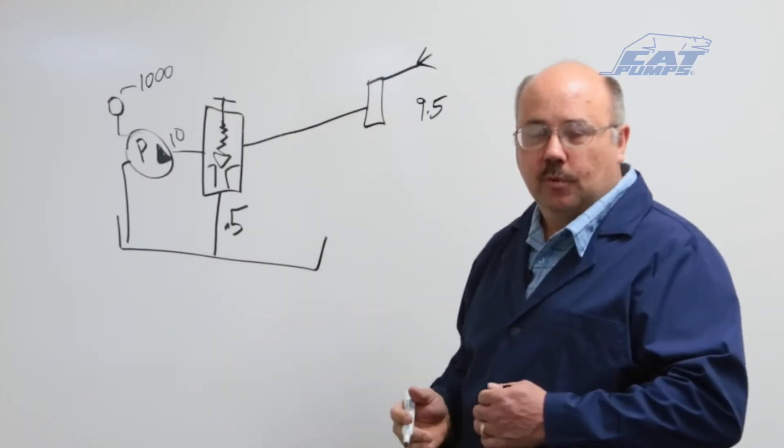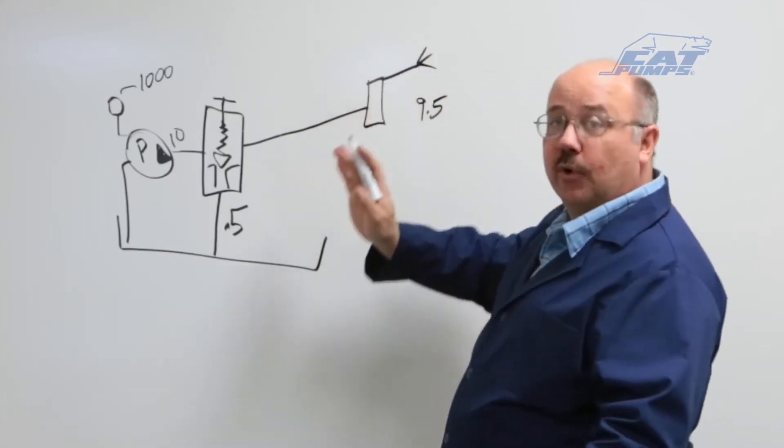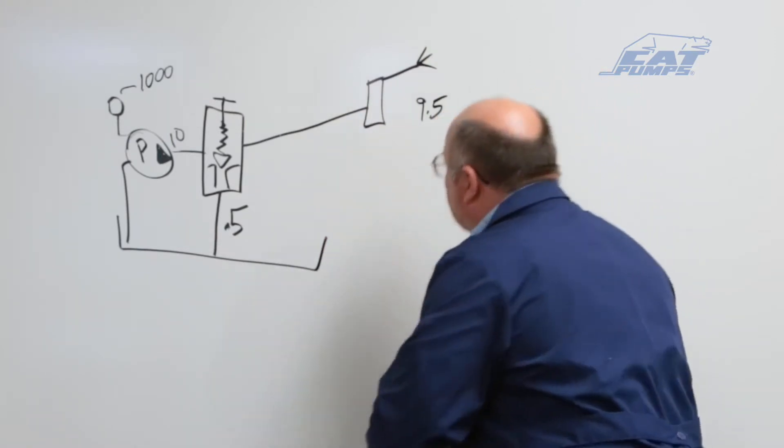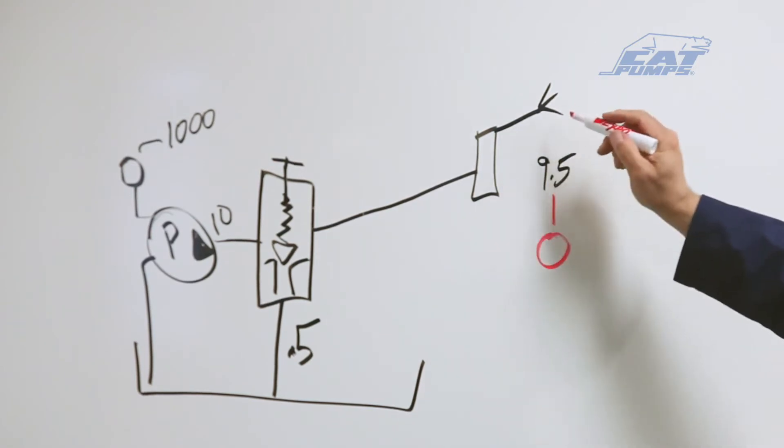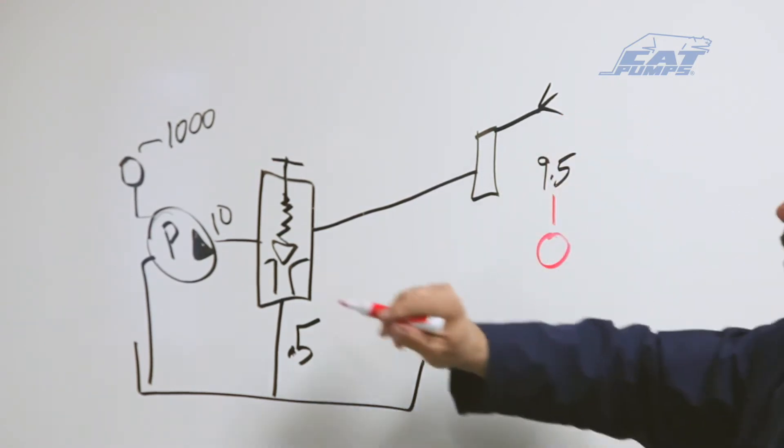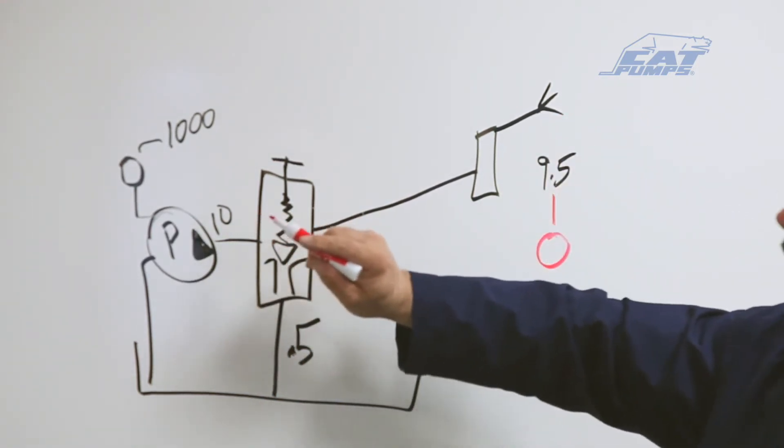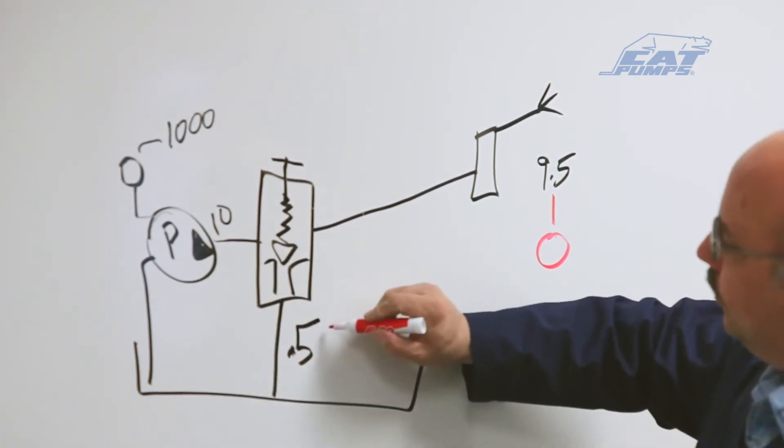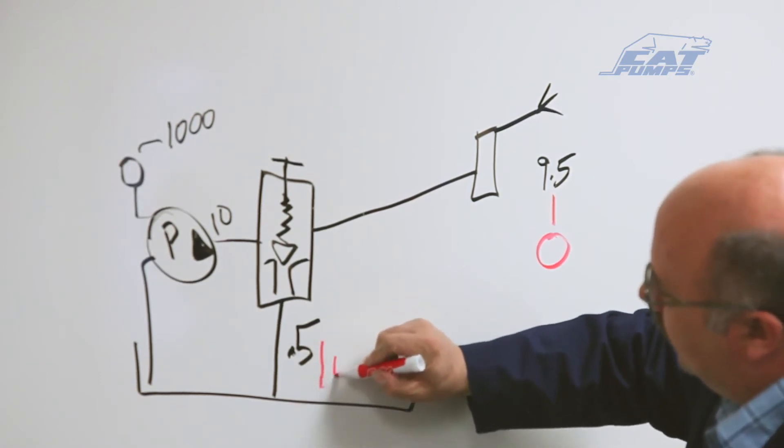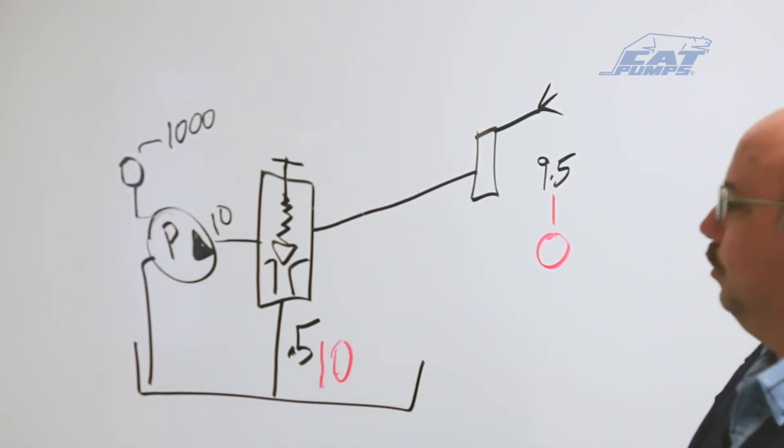Now the pressure override comes into effect when I release the trigger gun. What happens then is this flow will go down to zero because we no longer have any flow out here. This flow stays at 10 all the time—that's the definition of a positive displacement pump. So this flow here will change to 10 gallons per minute.